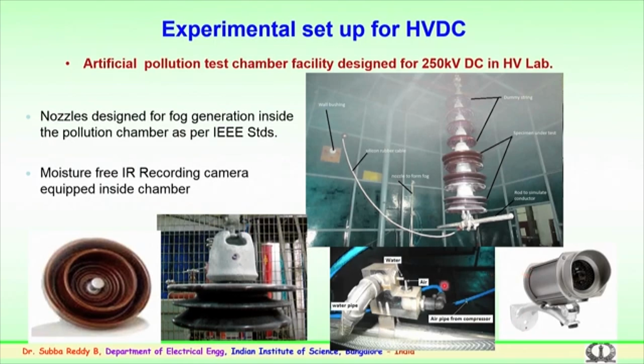The AC setup which was existing has been modified, and the same chamber, which is 5 meters by 5 meters by 5 meters, is being used. A typical experimental arrangement is shown here, wherein you can see the specially manufactured DC insulators being used. This is the high voltage, and this is the grounded. We have used various nozzles as per the IEEE standards to simulate the fog conditions or the rain conditions. Various insulators of various creepage lengths, particularly used for HVDC, are being used. In the laboratory, the facility has also been made using IR cameras to find out the location of the discharge activity during experimentation, when the pollution experiments are conducted for a long duration of time. As mentioned, the facility has been designed up to 250 kilovolts DC.